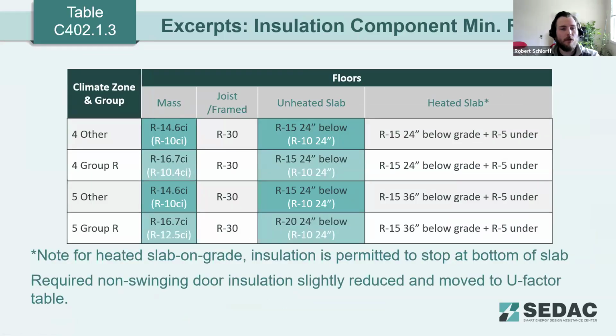Continuing on here, pulling out the floors. Again, the green cells highlight where changes have been made. White text shows the original 2018 values. So we see that the mass floor requirements and unheated slab requirements have been changed. One note here about heated slabs is that the insulation is permitted to stop at the bottom of the slab. The way that we interpret this footnote is to say that any heated slab should be wrapped, both perimeter, sides, and bottom, in insulation as a way of isolating it from the surrounding structure. This would be considered best practice. If that heated slab isn't fully wrapped, there can be thermal breaks between it and foundation walls or other elements that help some of the heat, or some of the energy that you're trying to heat that floor with, escape from the floor.